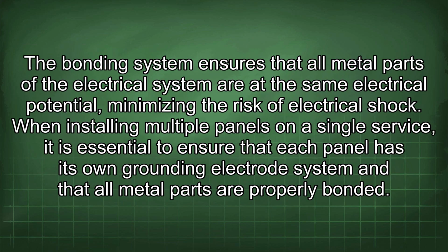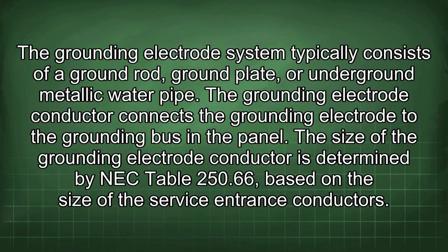The bonding system ensures that all metal parts of the electrical system are at the same electrical potential, minimizing the risk of electrical shock. When installing multiple panels on a single service, it is essential to ensure that each panel has its own grounding electrode system and that all metal parts are properly bonded. The grounding electrode system typically consists of a ground rod, ground plate, or underground metallic water pipe. The grounding electrode conductor connects the grounding electrode to the grounding bus in the panel.